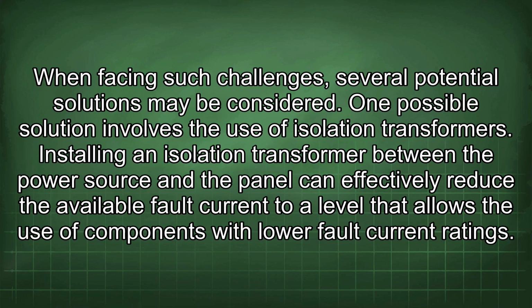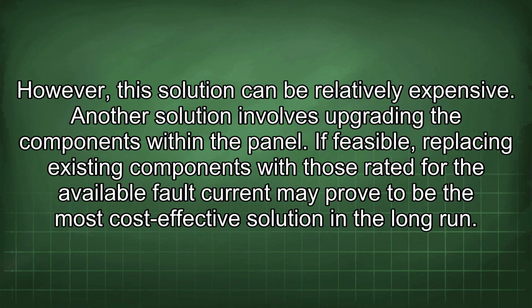When facing such challenges, several potential solutions may be considered. One possible solution involves the use of isolation transformers. Installing an isolation transformer between the power source and the panel can effectively reduce the available fault current to a level that allows the use of components with lower fault current ratings. However, this solution can be relatively expensive.